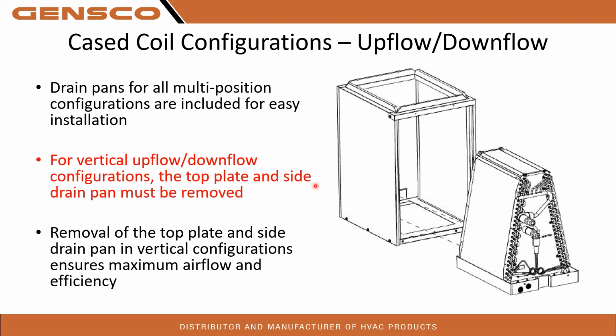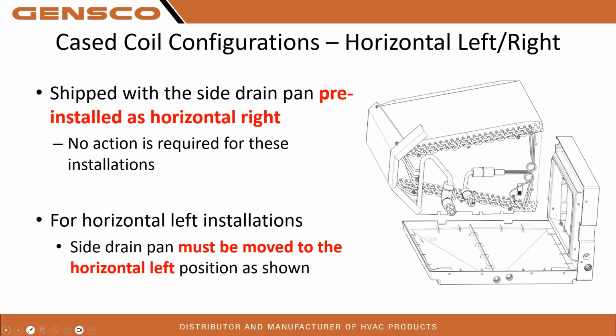You can see here we have an upflow downflow application. As you see in the picture, your horizontal drain pan and your top plate have been removed. This is an example of the horizontal left. Again, these units are pre-installed for horizontal right. So if you're going to change it to a horizontal left, you'll need to make sure to change your drain pan over to the other side there.